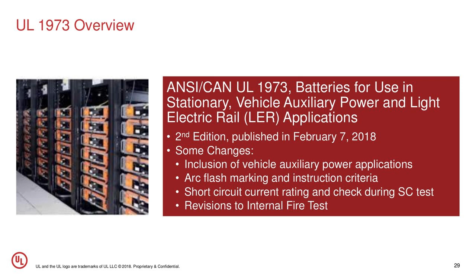We did some revisions to what we call the internal fire test, a very important propagation type test in UL. We changed the name to better represent what it means: it's now a single cell failure design tolerance test. We have two methods, one for lithium ion and one for other technologies like hot temperature sodium beta batteries, lithium metal, or lead acid. We also added an informative Appendix F providing methods that can be used to conduct the cell failure test.